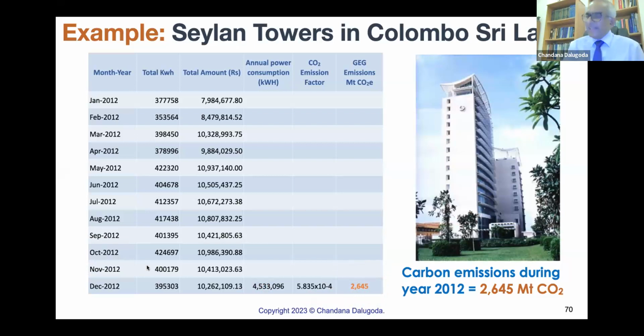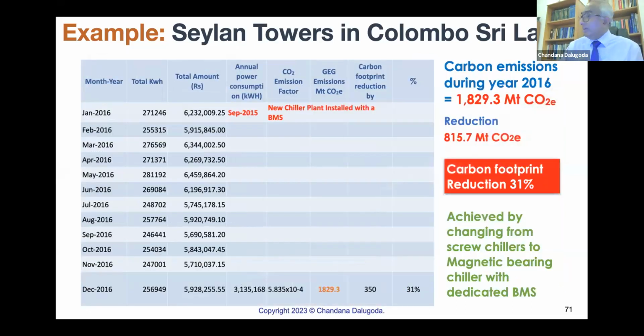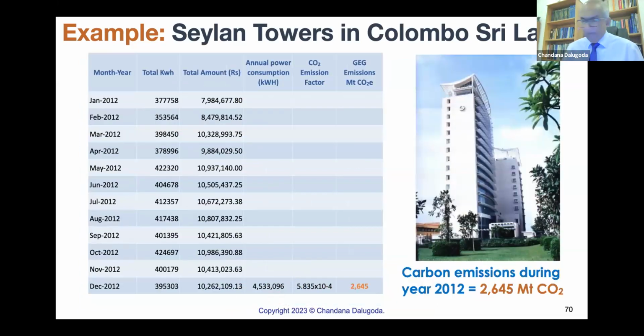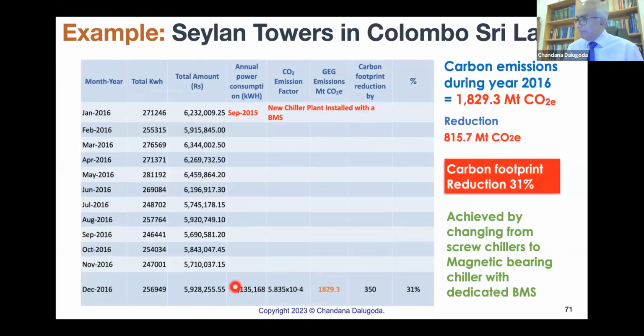Now, in 2015, they replaced it with a magnetic bearing chiller, plus a dedicated BMS, building management system, with energy saving strategies. See what happened. The total annual power consumption is now 3.1 million. Earlier, what was it? 4.5 million. Now it is 3.1 million. CO2 emission is 1,829.3, a 31% saving. So we call this a carbon footprint reduction of 31%. This is what we can do with the highest energy efficient equipment plus BMS.